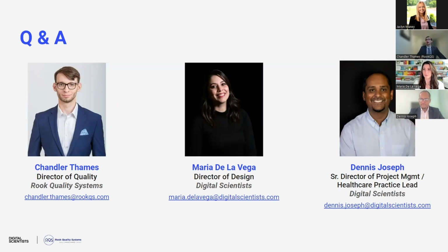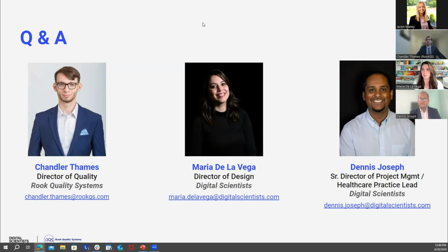So for Chris Miller, who asked how IEC 62304 for software ties into IEC 62366 usability in terms of risk management: very good question. 62304 mandates including an ISO 14971 risk management process. That's the big standard for medical device risk management. So in having to adhere to 14971, you definitely want to make sure that you're accounting for any use case related risk. And those risks should tie into your usability study, right? So you should be outlining this usability study based off of the use-related risk assessment that you've performed for the device software.